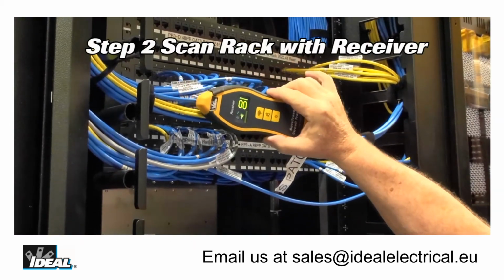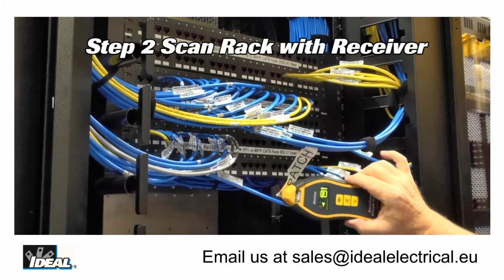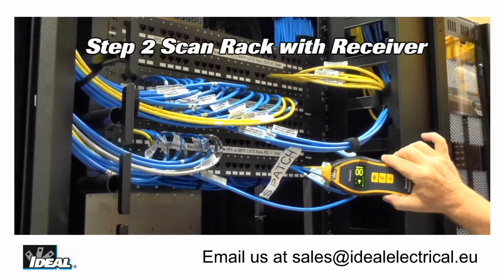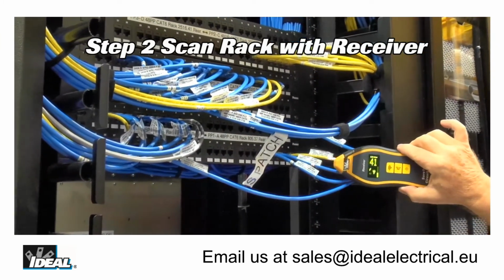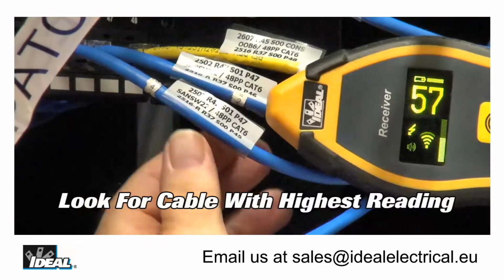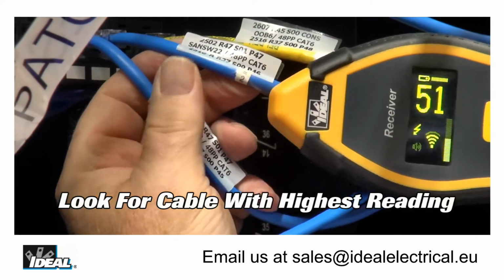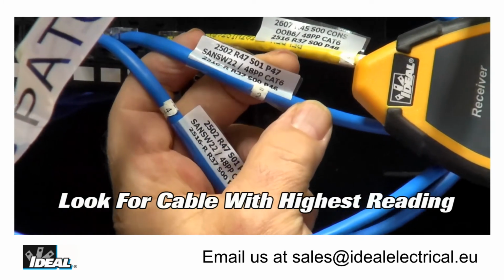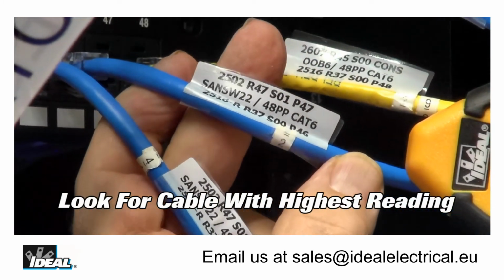Step two is to go to rack number 2516, and using the receiver, slowly scan all the cables in the rack using the highest sensitivity mode. Hold the receiver in line with the cable to get the strongest signal possible, and then reduce the sensitivity to properly locate the correct cable in the rack.